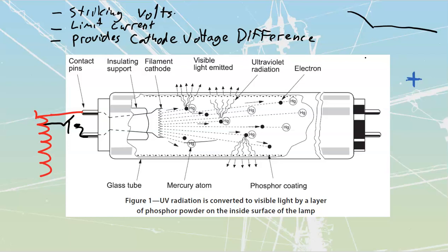What happens is when this stuff is manufactured and shipped, mercury is really heavy. So the mercury is going to tend to accumulate along the bottom, especially with the vibration that happens during shipping. If those things were stored horizontally or even vertically, all the mercury is going to end up at one end or the other. We need that to move out and across all the tubes fairly evenly.